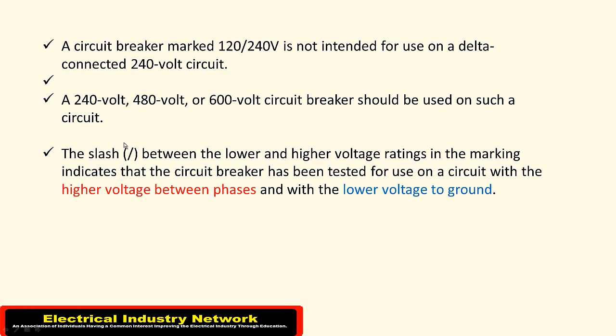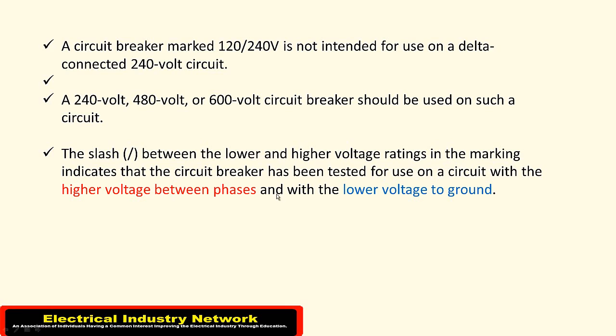The slash between the lower and higher voltage ratings in the marking indicates that the breaker has been tested for use on a circuit with the higher voltage between phases—A to B, B to C, C to A—and with the lower voltage to ground—A to ground, B to ground, C to ground.